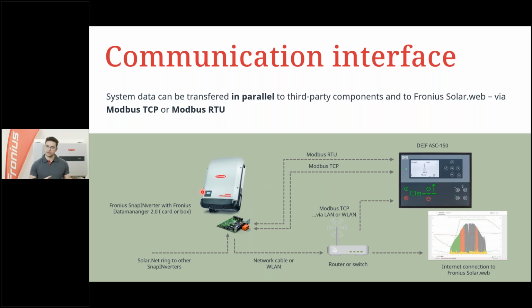Now, it looks very similar on the Fronius Snap Inverter range. The only difference is here that there will be products out there with no Datamanager card integrated. We are talking here about a light version. And this is fine like that because you only need one Datamanager and can connect multiple inverters to it with a so-called Solar Net ring. It's a simple in and out connection with a standard Ethernet cable, and you simply go through, connect all of the light versions to one master with the Datamanager card integrated.